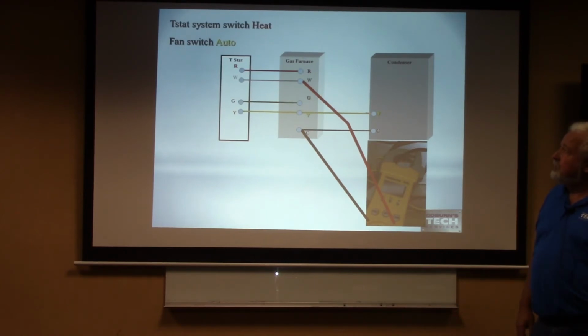All right, let's go to the W and C in heating on the auto. Should my gas valve be kicking in? Yep, should be. So I should see 24 volts. What about the G in the heating? What's going to bring on that circuit? Yeah. I could read 0 there, depending on if the fan temperature sensor is bringing it on, or whether it's actually being brought on by the board. Absolutely. So what about the Y circuit right there? Good, I'll see 0 right there as well.